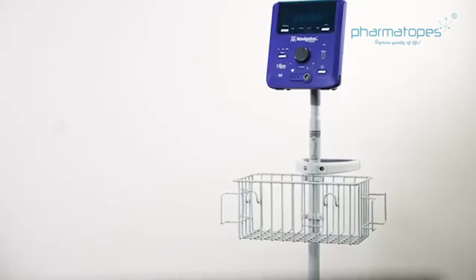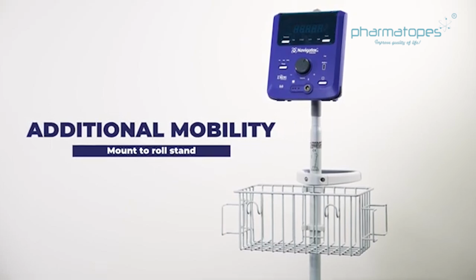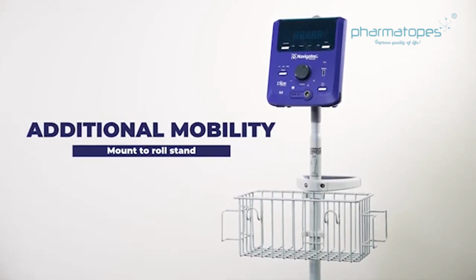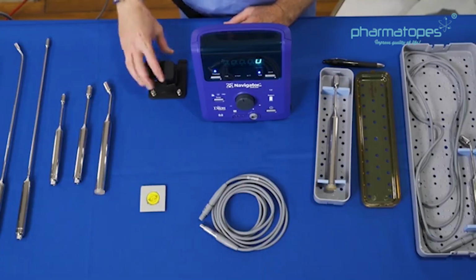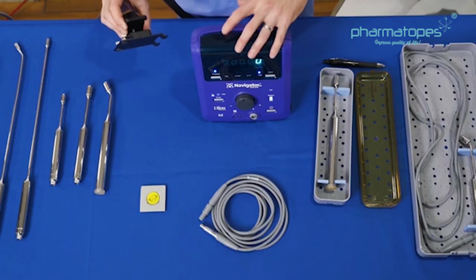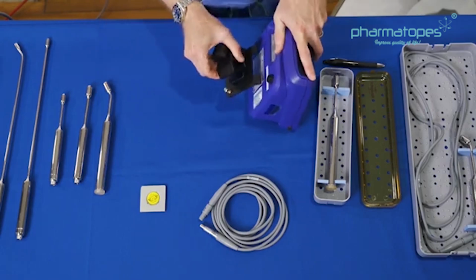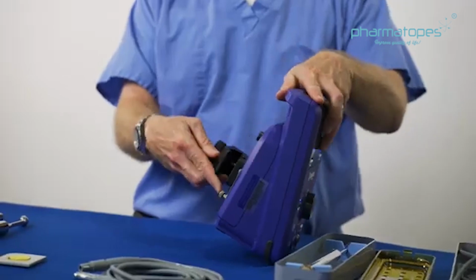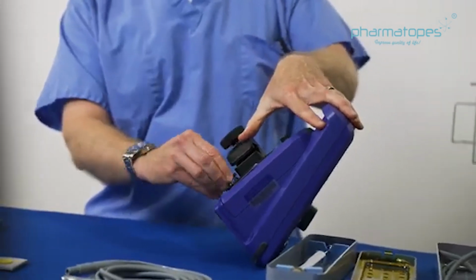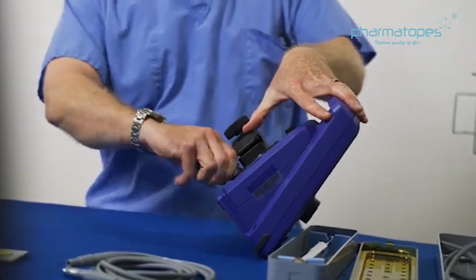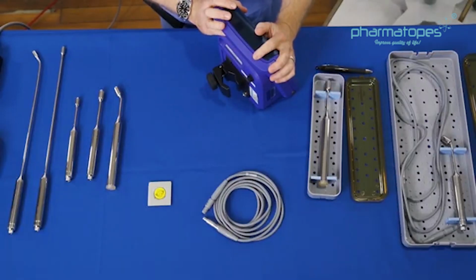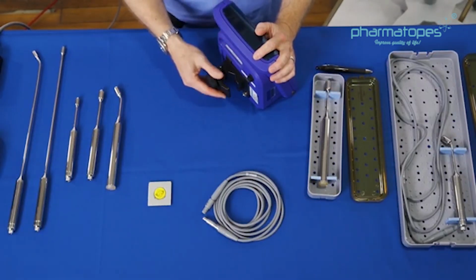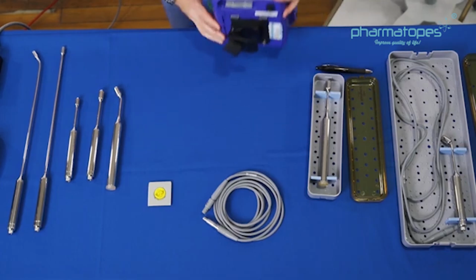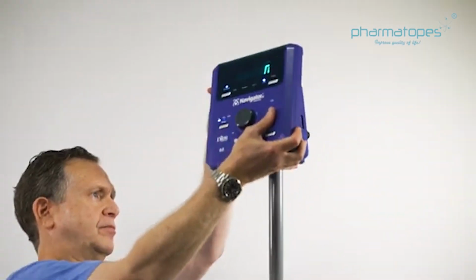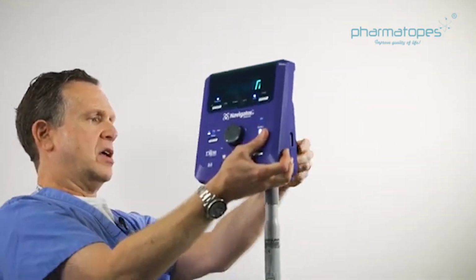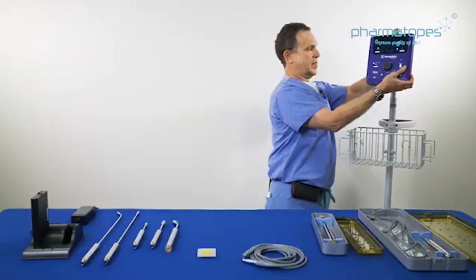the room. As previously mentioned, for additional mobility, the control unit can be attached to the Navigator roll stand. First, attach the pole clamp to the control unit by inserting the top ears into the back of the control unit and gently screw down the clamp to the system. Now the control unit is ready to be mounted on the roll cart. Open the knob and place the control unit at the desired height. Tighten it down into position.